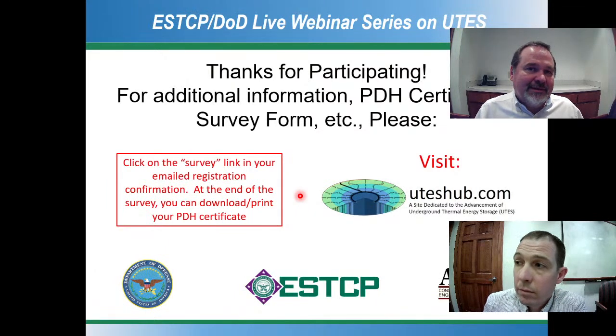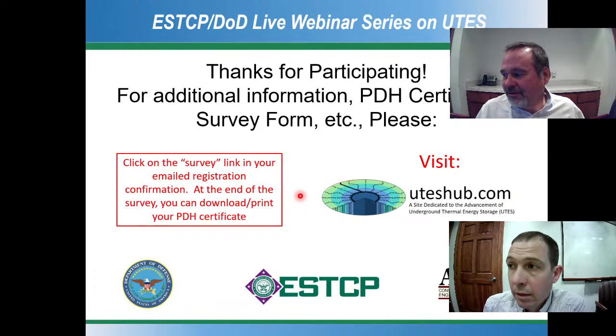So we're down to 1/6 of the capacity. We've got a 6-to-1 turndown, and we can live with that. But if you just had one big humongous pump in there, you'd be stuck at 50% turndown. So that is kind of a unique thing about the closed loop systems. Open loop, I'm sorry, the open loop systems.